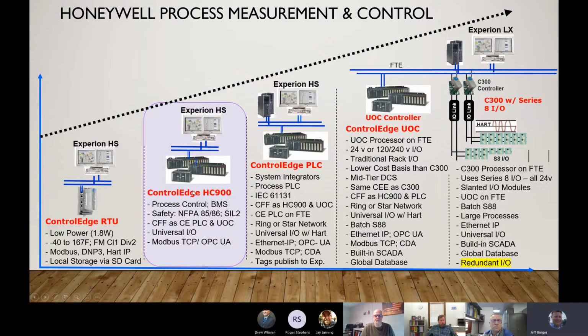The next one up is the ControlEdge HC900, and this is known as the hybrid control HC900. This controller takes process control, logic control, and safety control, and embeds it into the CPU as a hybrid control system that allows control over all three of those areas. This typically is used in SIL applications that require burner management systems. So it's FM, NFPA 85, 86, and SIL 2 rated.